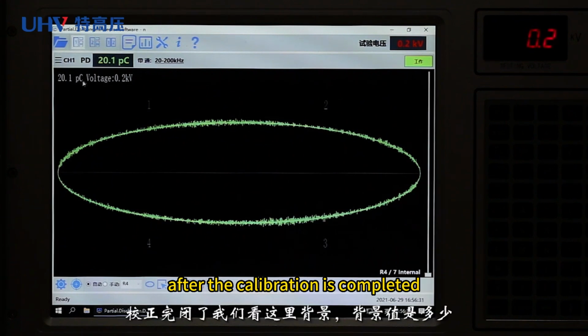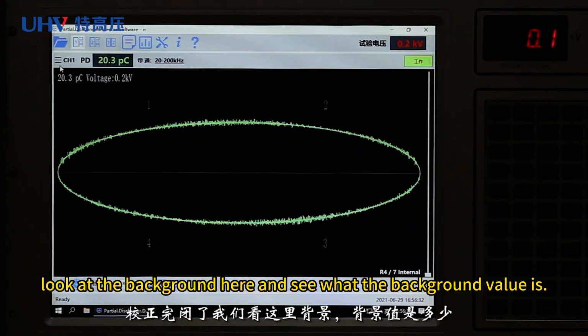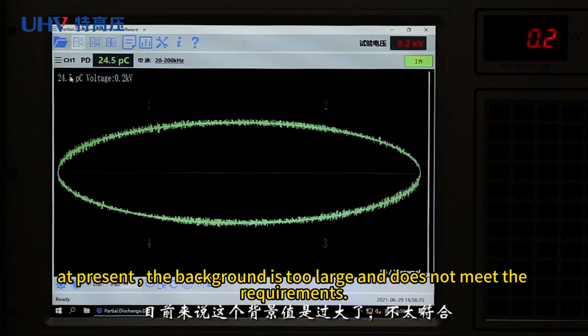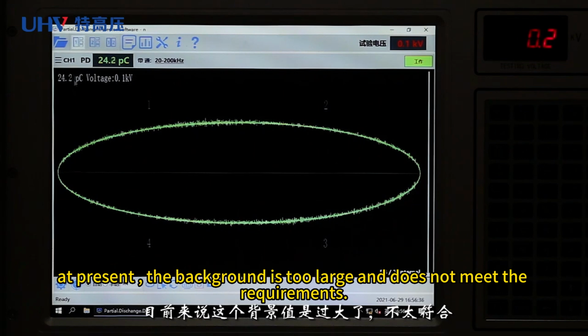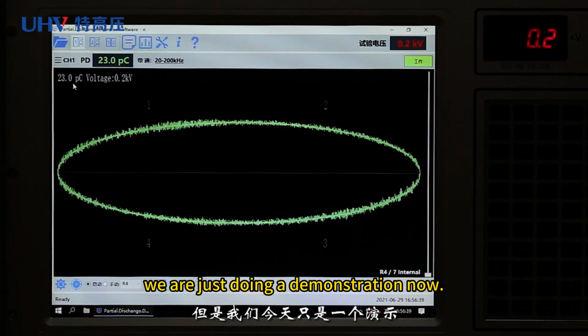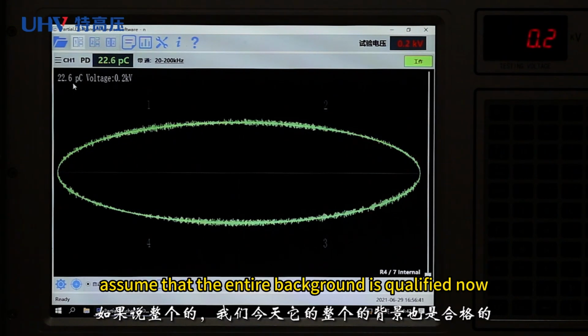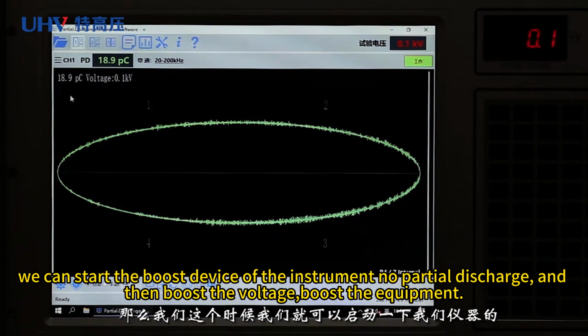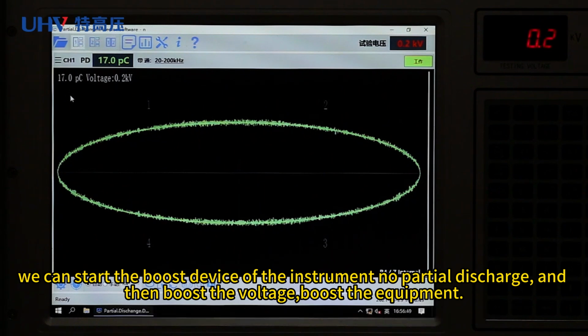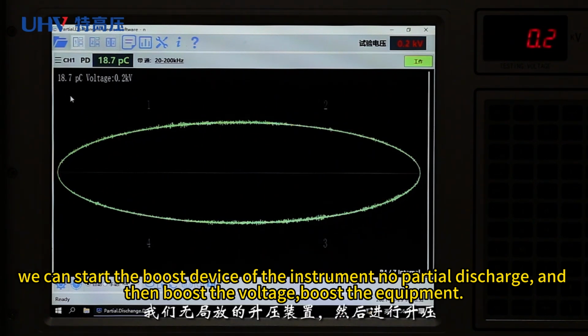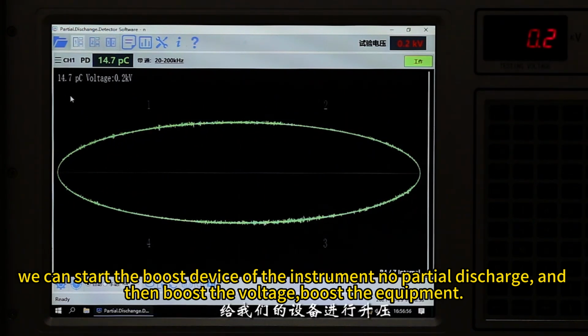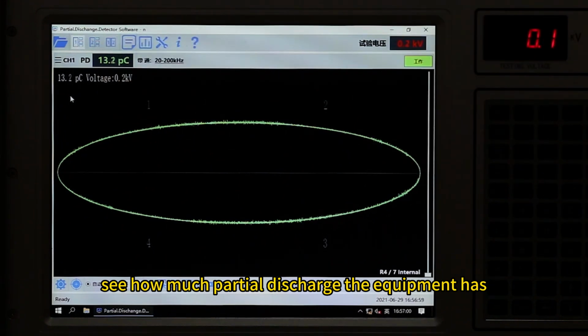See here. After the calibration is completed, look at the background here and see what the background value is. At present, the background is too large and does not meet the requirements. We are just doing a demonstration now. Assume that the entire background is qualified now. We can start the boost device of the instrument, no partial discharge. And then boost the voltage, boost the equipment. See how much partial discharge the equipment has.